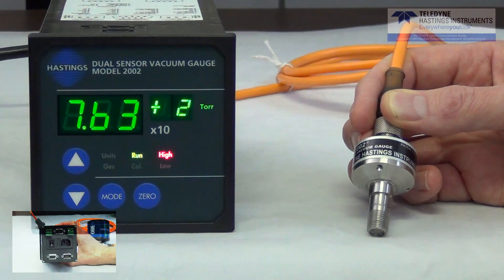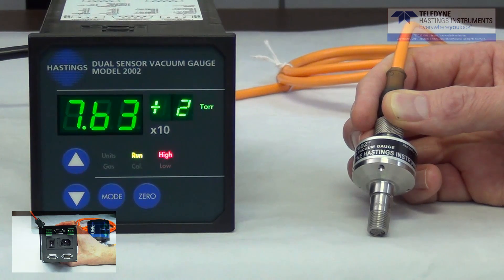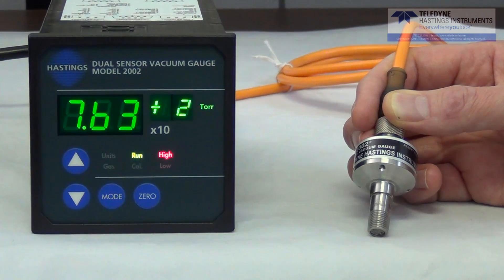Now the microprocessor is always monitoring the micromachined sensors. The instrument uses the signal from the piezoresistive sensor from atmospheric pressure down to 32 torr. Below 8 torr, the output from the thermal sensor is used. And in between 8 and 32 torr, the microprocessor calculates a weighted average between the two sensors to give a smooth transition. The user never sees the crossover.